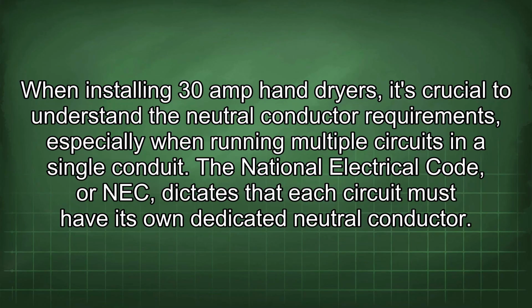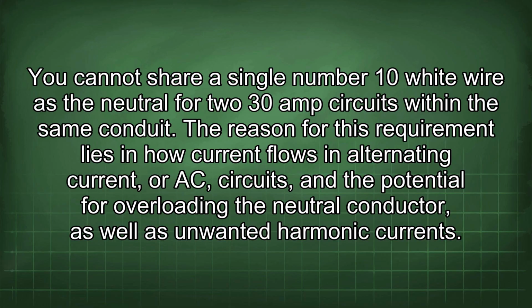When installing 30 amp hand dryers, it's crucial to understand the neutral conductor requirements, especially when running multiple circuits in a single conduit. The National Electrical Code, or NEC, dictates that each circuit must have its own dedicated neutral conductor. You cannot share a single number 10 white wire as the neutral for two 30 amp circuits within the same conduit. The reason for this requirement lies in how current flows in alternating current, or AC, circuits and the potential for overloading the neutral conductor as well as unwanted harmonic current.